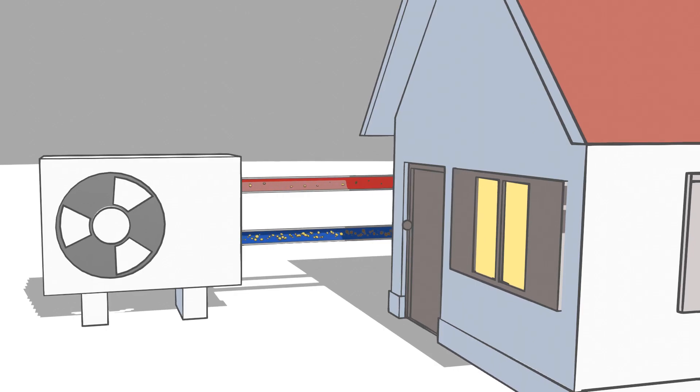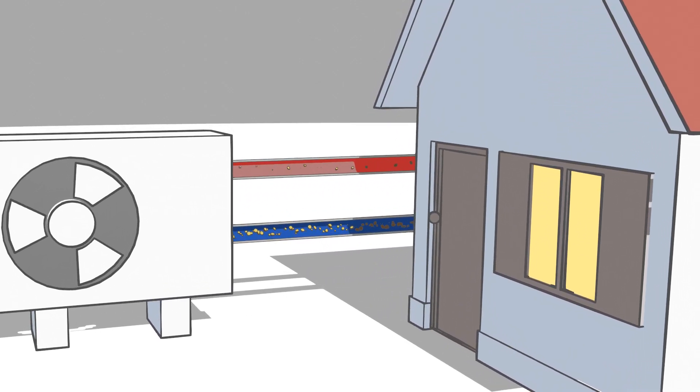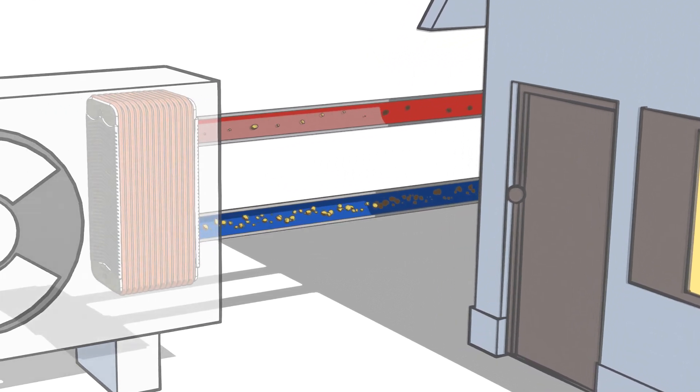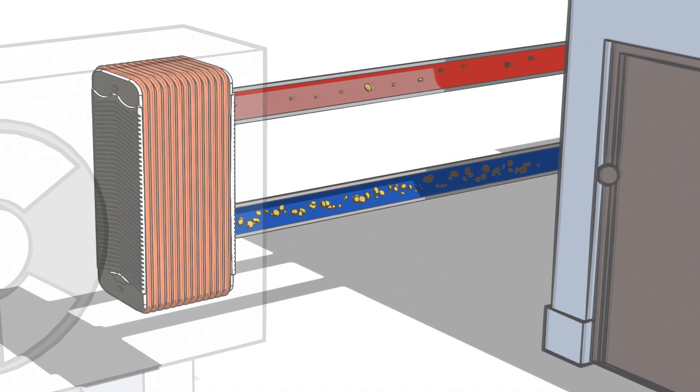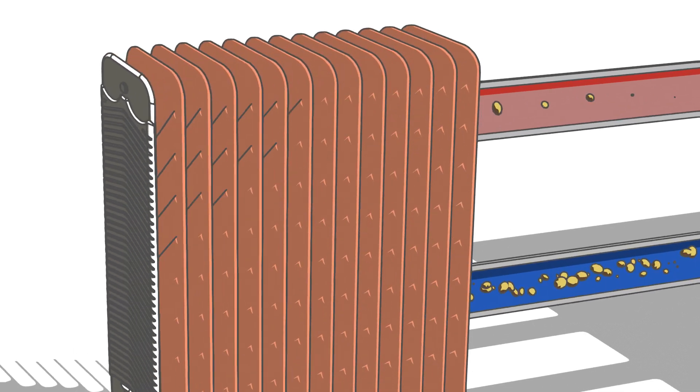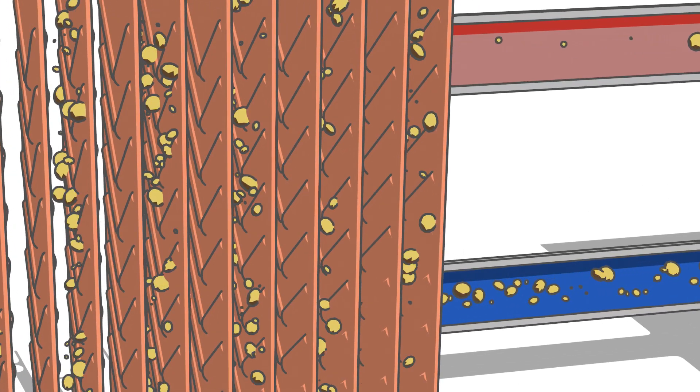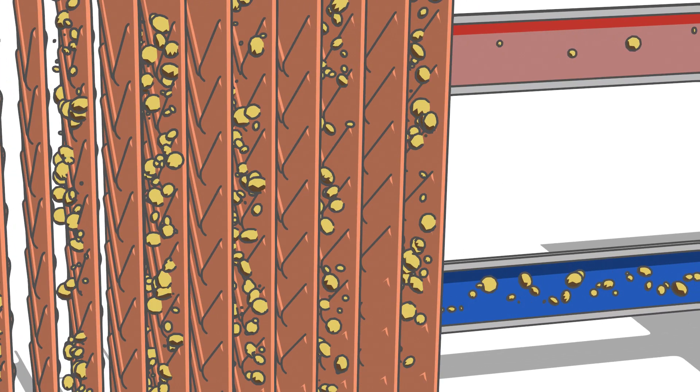One major threat to heat pump operation arises from impurities present in hydronic systems. Specifically, heat exchanger performance is highly sensitive to water quality, and deposits and scale buildup can have a damaging effect on efficiency and consumption levels.